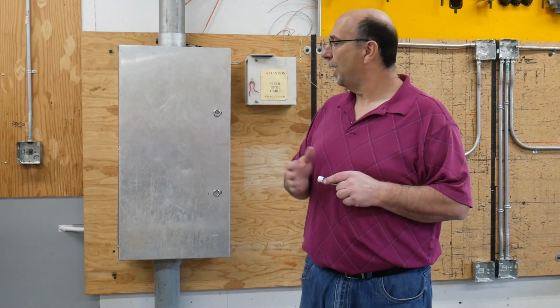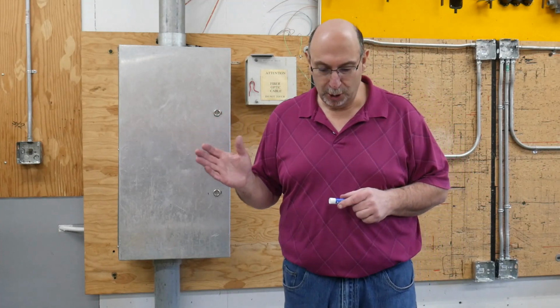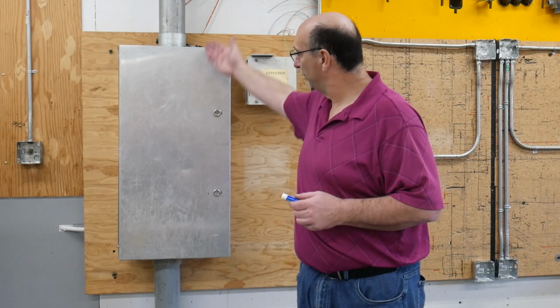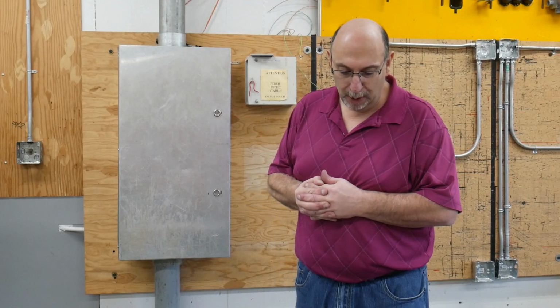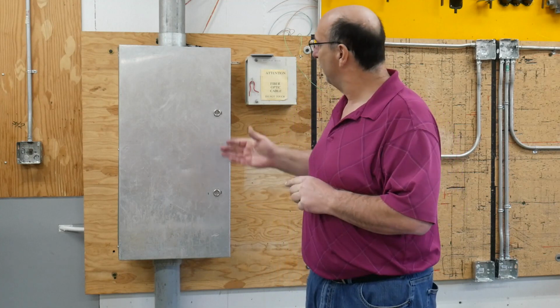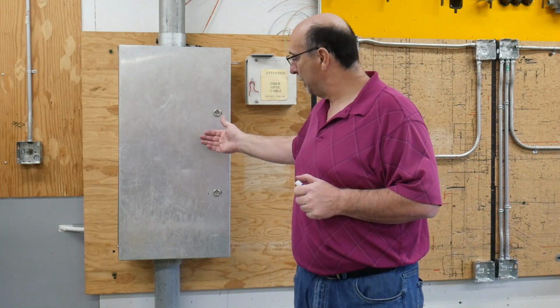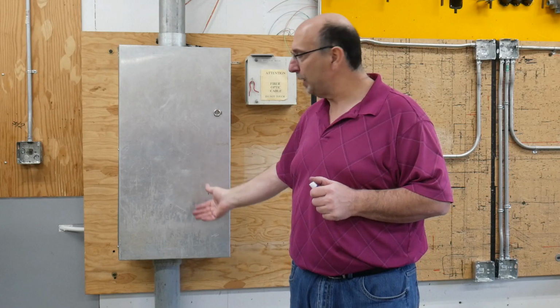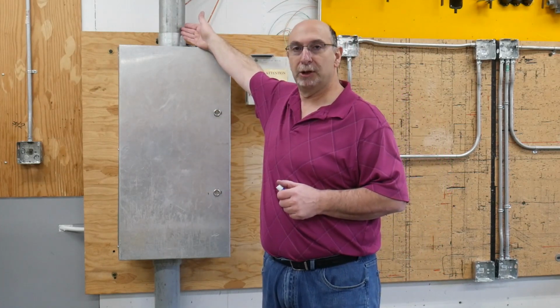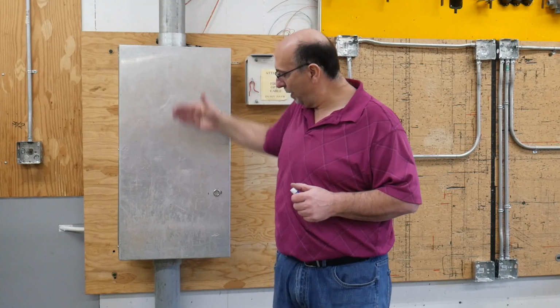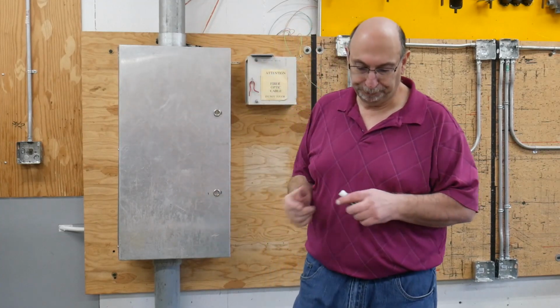Welcome back to 12-3036 pull box or junction boxes. By far the easiest calculation to do is the straight through pull. So have a look at 12-3036 subrule 2A in your code book on page 168. In this example, what we're doing is determining the size of the pull box, or the length of the pull box, when we have two 4-inch conduits, one entering on the top and one entering on the bottom.